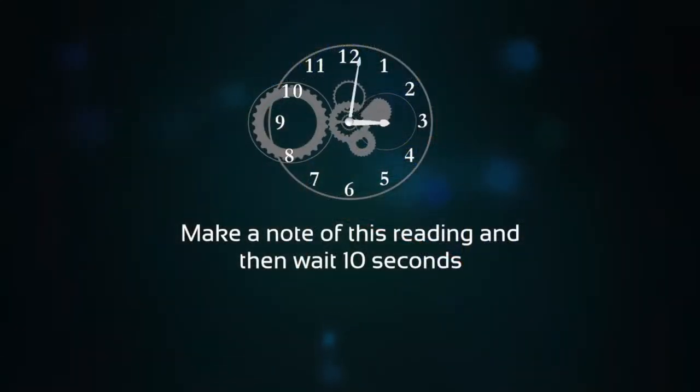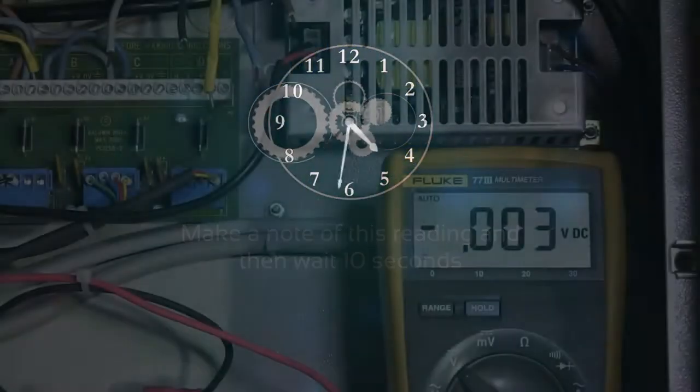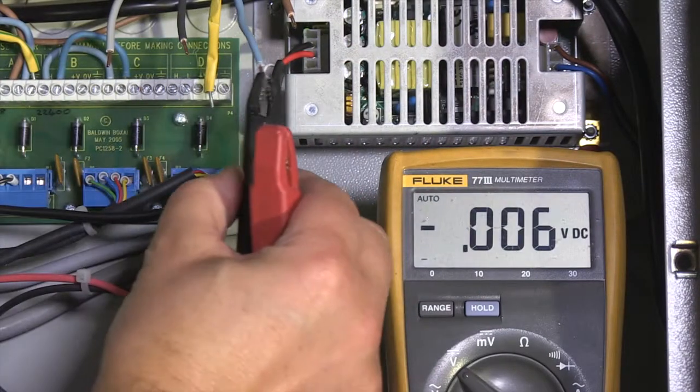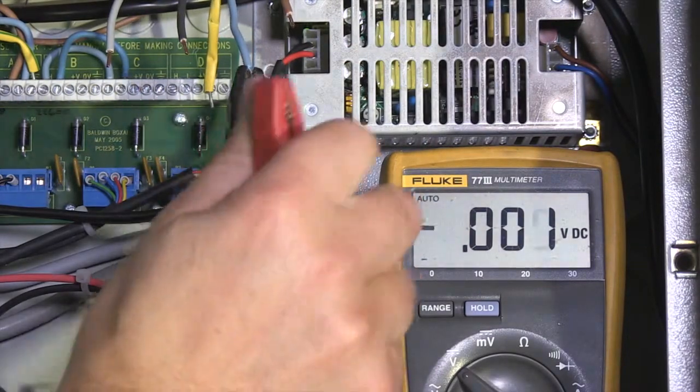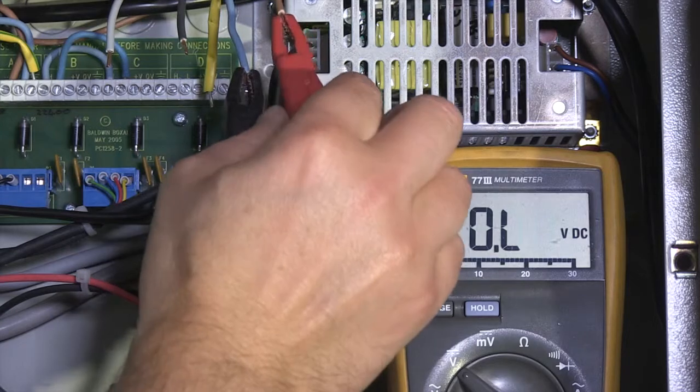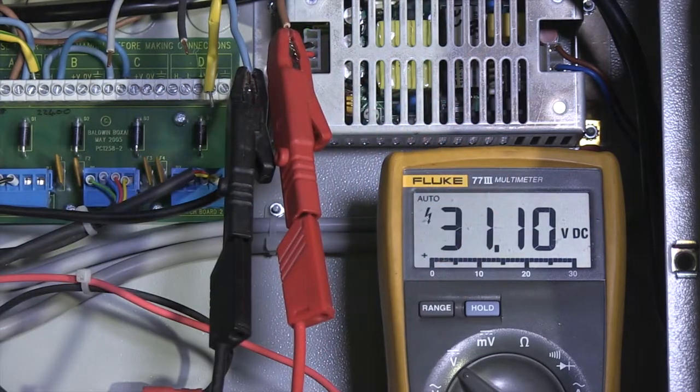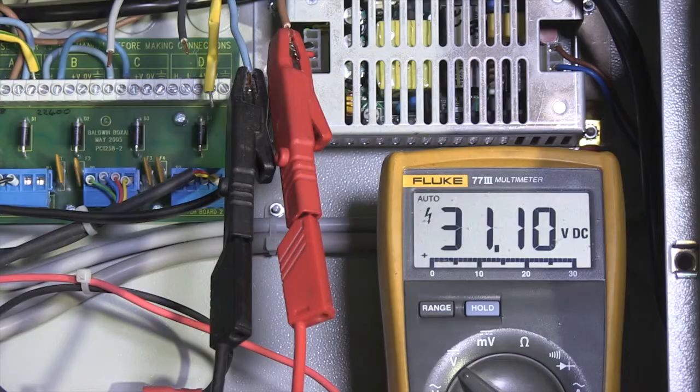You will need to make a note of this reading. Wait for 10 seconds and then measure the return voltage on the 0 volts and plus volts on the return cable. This should be no more than 8 volts lower than the reading at the A terminals.